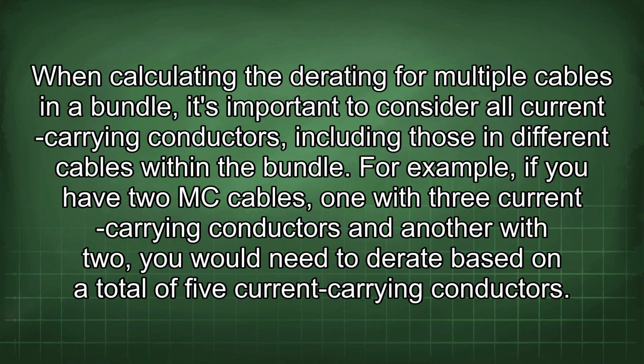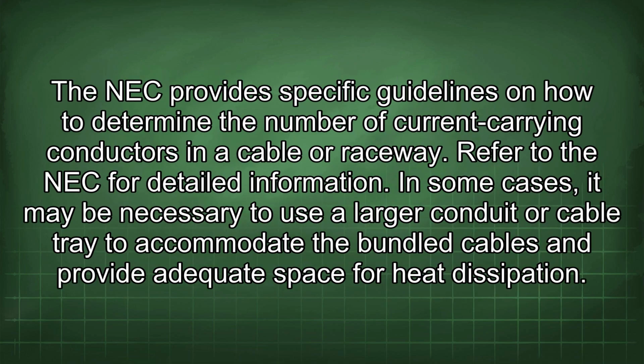When calculating the derating for multiple cables in a bundle, it's important to consider all current carrying conductors, including those in different cables within the bundle. For example, if you have two MC cables, one with 3 current carrying conductors and another with 2, you would need to derate based on a total of 5 current carrying conductors. The NEC provides specific guidelines on how to determine the number of current carrying conductors in a cable or raceway. Refer to the NEC for detailed information.